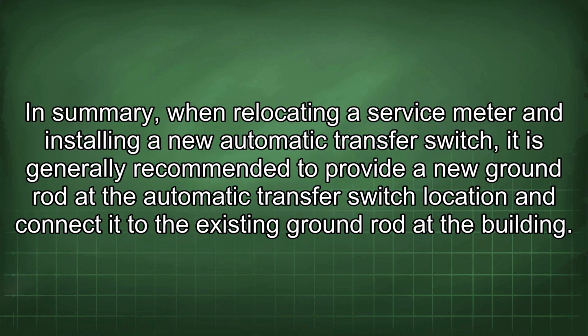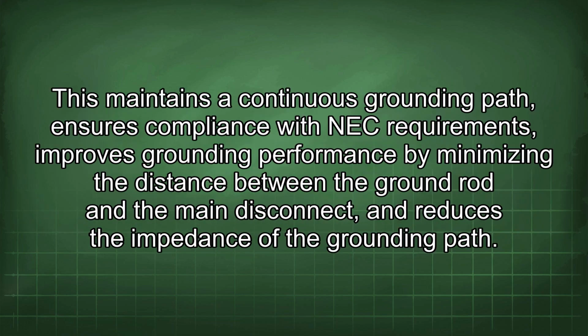In summary, when relocating a service meter and installing a new automatic transfer switch, it is generally recommended to provide a new ground rod at the automatic transfer switch location and connect it to the existing ground rod at the building. This maintains a continuous grounding path, ensures compliance with NEC requirements, improves grounding performance by minimizing the distance between the ground rod and the main disconnect, and reduces the impedance of the grounding path.